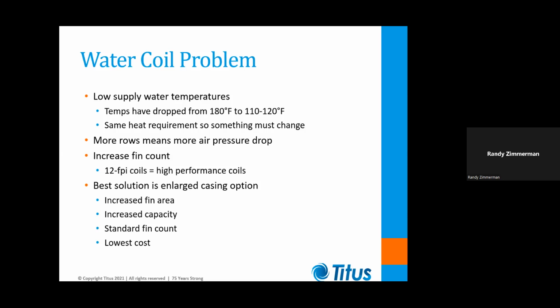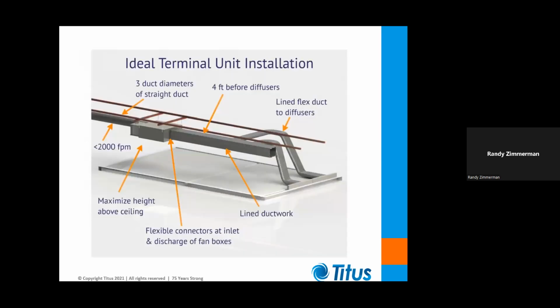That gives you more fin area, which is the best way to increase our capacity because we're getting to use a standard coil. We don't have to increase our fin count. We don't have to do anything fancy. We're just going to upsize the casing to put a larger coil on a smaller inlet duct. It's the most efficient way to get back to the capacity we need without increasing the number of rows, without increasing the air pressure drop. It's just the best way to do it.